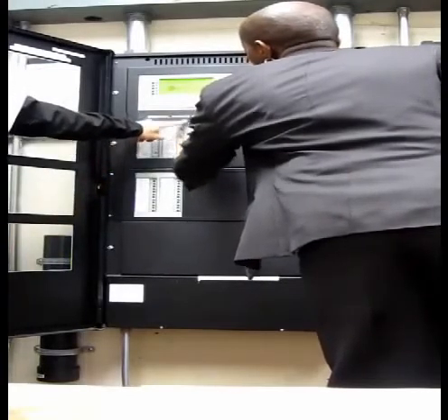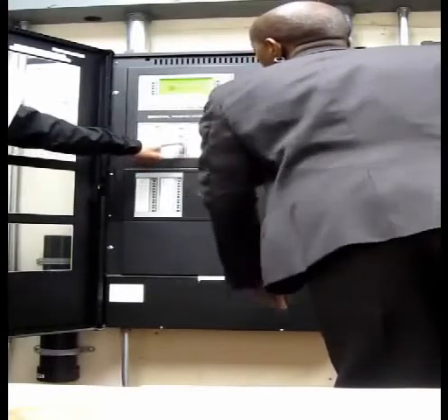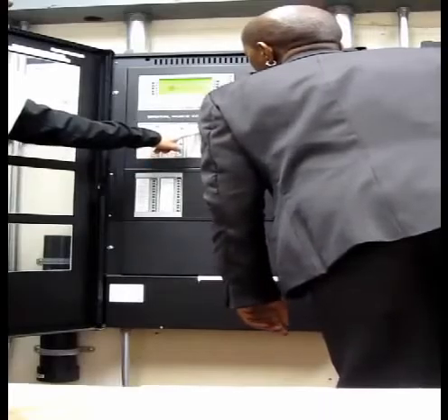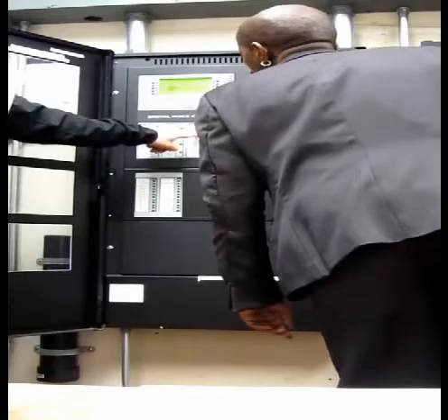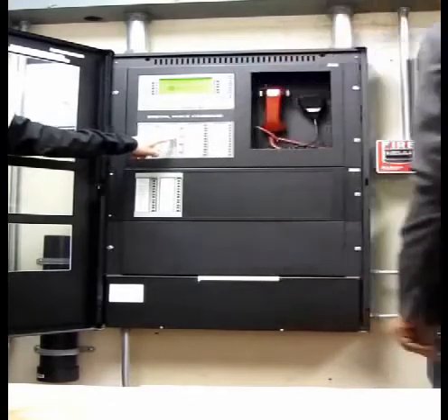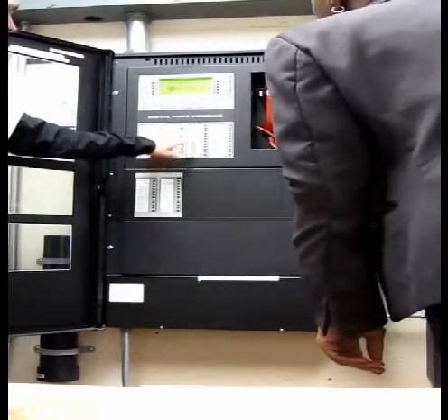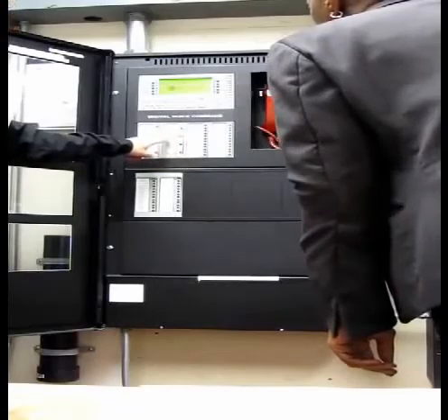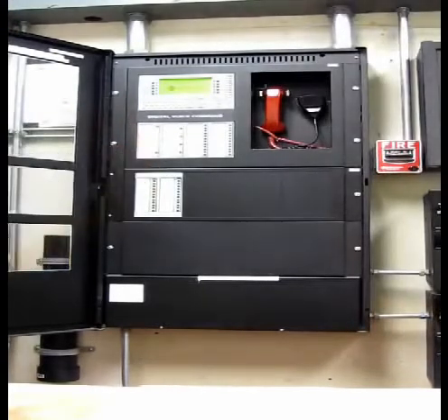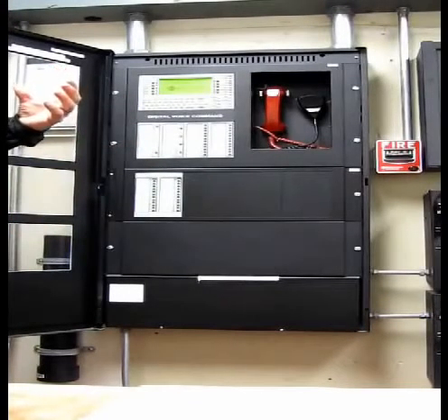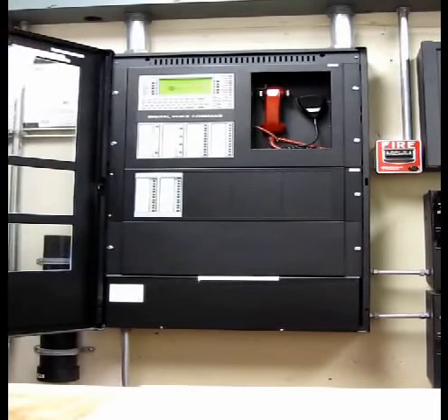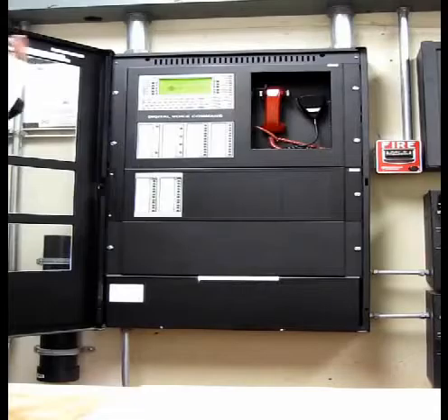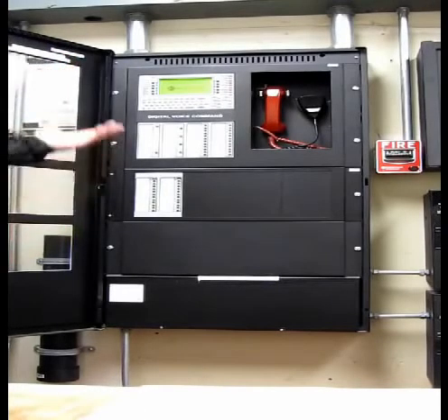This one's an all-call. This will light up everything. And this one will just do, for example, if you have the 3rd floor going off in alarm, it's going to activate 2nd, 3rd, and 4th automatically, per the sequence of operations. Okay. So what this does, by pushing this button, instead of activating all of them, it just activates 2nd, 3rd, and 4th. It pages the active evac alarms. That's an easy way, for example, if the 3rd floor is a false alarm and you know it, you can hit that button and just talk to 2nd, 3rd, and 4th and say, hey, there's been a false alarm reported in the building. You guys can go about your business and then reset the system.